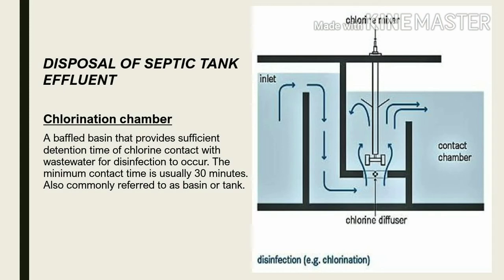And last is the disposal. Disposal means the septic tank effluent is disposed to the external part of the septic tank, and it is done by the chlorination method and a chamber which is called the chlorination chamber. A baffled basin provides the sufficient detention time of chlorine contact with wastewater for disinfection to occur. The minimum contact time is usually 30 minutes. Also commonly referred to as the basin or the tank.